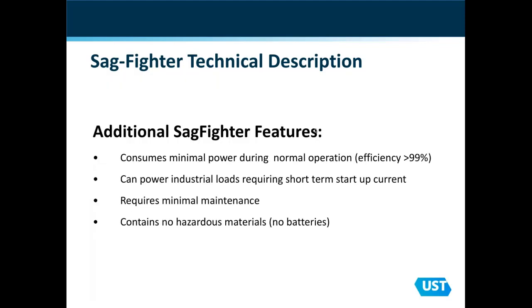Additional features, it's very efficient, operates at 99% because it's primarily sitting in bypass a majority of the time. We can power industrial loads. With our high inrush capabilities, it's an excellent application for industrial type environments. Very little maintenance, again, very few moving parts, and there's no hazardous materials or batteries on board or involved with the installation.